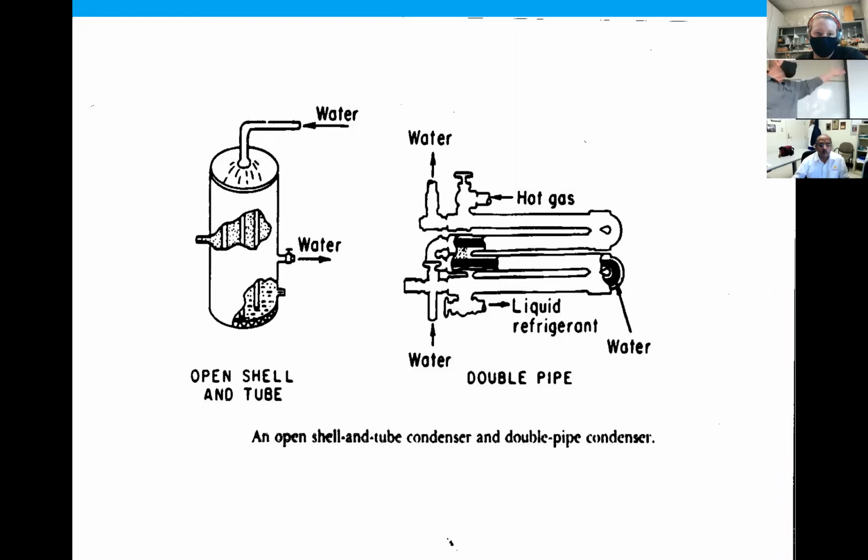So then you're going from colder water to warmer water. A lot of places, what will happen, that water then gets put into a holding pond and they may recycle that water and let nature remove that heat into the atmosphere, especially in a colder climate. Someplace that's really warm, it may not be the best, but cold climate, because if you do go by some processing plants, you'll see ponds of water next to them in the dead of winter and they aren't froze. That's because they're utilizing that water as part of their system.